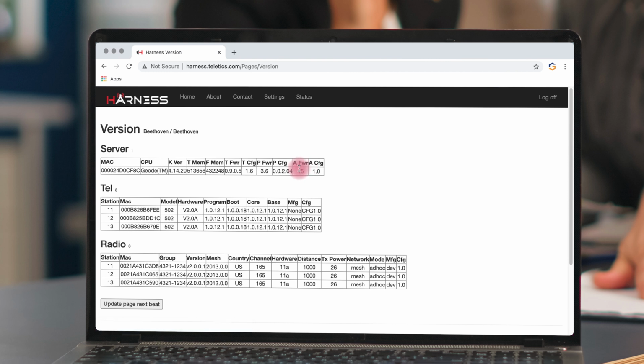Version is the firmware levels as well as the software that was used to do programming and configuration, both at the factory and also at the field level. So one example might be that if you have a field technician that's using an old version of programming software, and whatever he's doing is creating a problem for individual sites, you can look at all of your sites and find out where that happened and make corrective action on a bulk basis rather than doing it individually. And it gives you a complete audit trail of anything that's been done at any particular site.